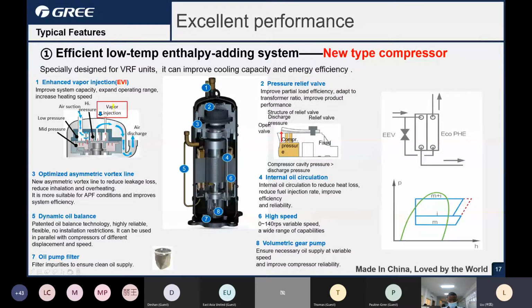Okay, so the first one, EVI, has a very big difference from the other ordinary compressor. Let's look at this graph. You can see here with the EVI feature, the unit can save power consumption and also get very good compression. That means you get more cooling or heating performance, however, the power consumption is less. The power consumption of the compressor is less than the ordinary compressor. That's the advantage of the EVI compressor.